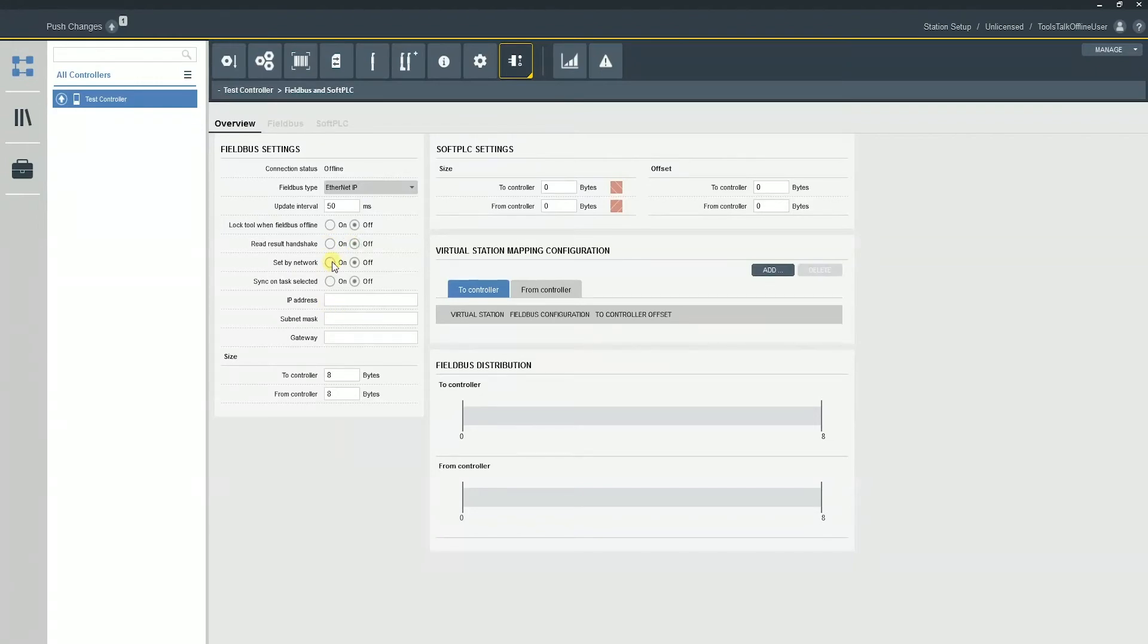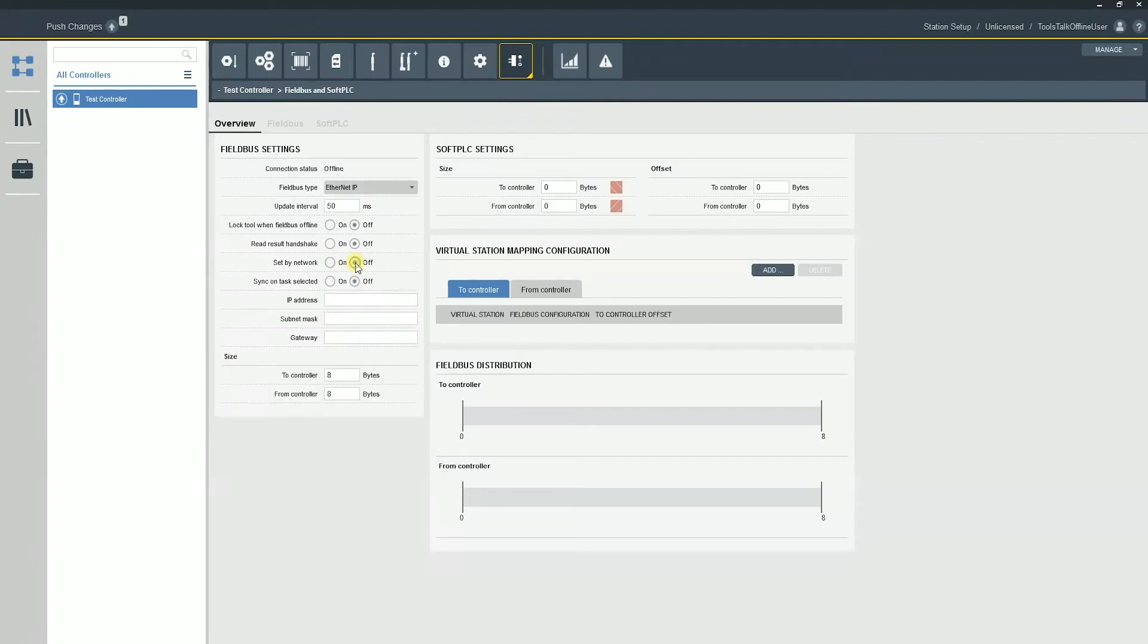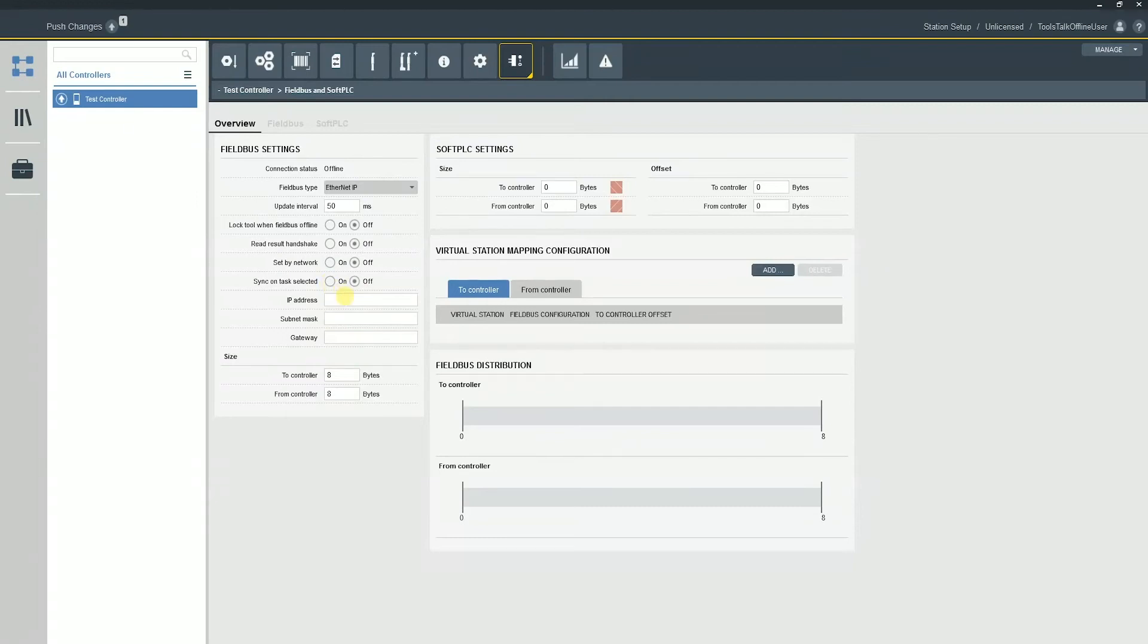So set by network, Ethernet IP does have the option to have the PLC send us the actual IP address, so keep that in mind. If we do want them to set the IP address, we can just turn that to on. And then we also have sync on task selected. So what this means is that if you change the task while on the virtual station while we're connected to the PLC, it's going to resync the task that's assigned.